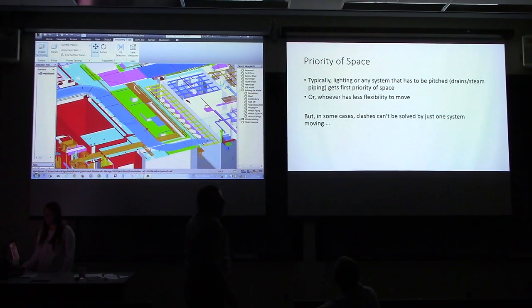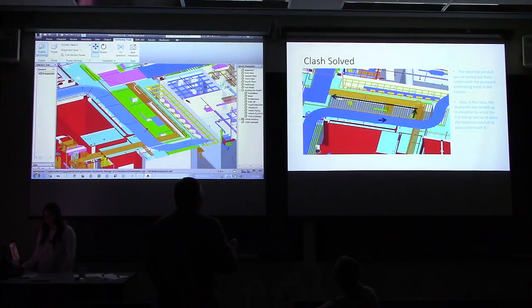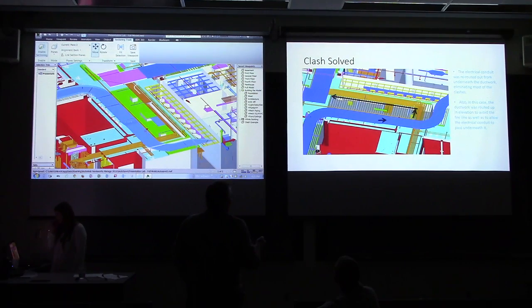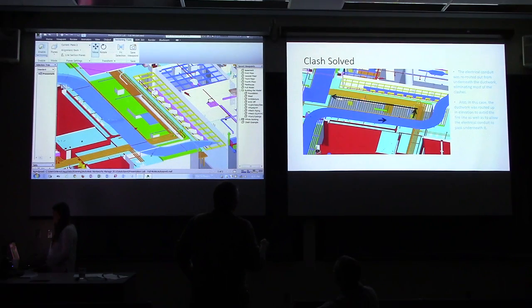Sometimes it's just not simple to say move the duct, move the pipe. So as a collaboration, as a team, we figure out the best process for doing it. In this example, we moved the conduit down, or moved it over, giving it a different route. We ran the ductwork up to clear over top of the conduit and the fire protection pipe, as well as dropped the fire protection pipe so it would get under the ductwork as it went out the other side of the building.